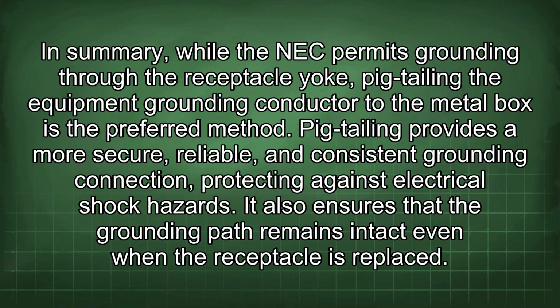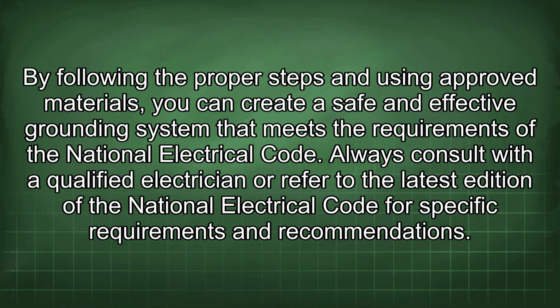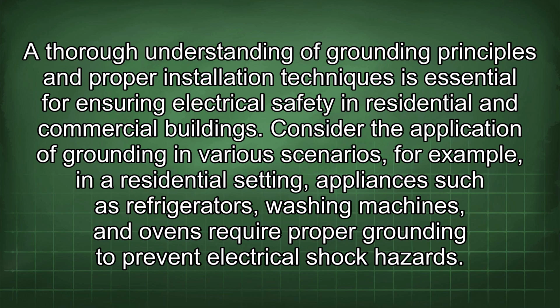In summary, while the NEC permits grounding through the receptacle yoke, pigtailing the equipment grounding conductor to the metal box is the preferred method. Pigtailing provides a more secure, reliable, and consistent grounding connection, protecting against electrical shock hazards. It also ensures that the grounding path remains intact even when the receptacle is replaced. By following the proper steps and using approved materials, you can create a safe and effective grounding system that meets the requirements of the National Electrical Code. Always consult with a qualified electrician or refer to the latest edition of the National Electrical Code for specific requirements and recommendations.